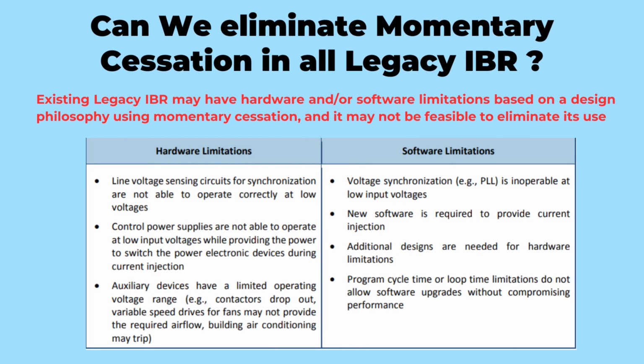Now, let's dive into the intriguing question of whether we can bid farewell to momentary cessation in these legacy inverters. Legacy inverter-based resources, IBR, often possess hardware and software limitations that stem from a design philosophy reliant on momentary cessation. These limitations can make it challenging or even infeasible to eliminate its usage altogether. One hardware limitation arises from the line voltage sensing circuits used for synchronization. These circuits may struggle to operate accurately at low voltages due to voltage distortion, phase jumps, and harmonic issues. This poses a significant hurdle in eliminating momentary cessation. On the software side, a similar issue can be observed in the voltage synchronization control, specifically the phase-locked loop, PLL. At low voltage levels, the PLL may become inoperable, further complicating the elimination of momentary cessation. These are just a couple of examples highlighting the hardware and software challenges faced by legacy IBRs. It's crucial to address these issues to pave the way for advancements in inverter technology.